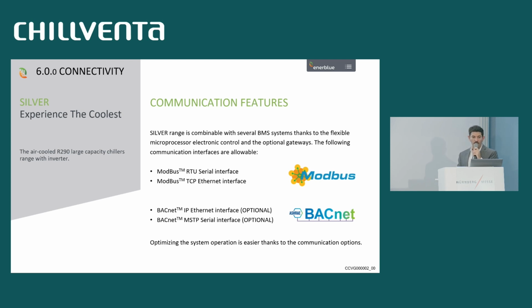Concerning the communication protocols, the unit is able to communicate via Modbus RTU or TCP/IP, as well as via BACnet IP or MSTP, which is a standard for our sector. The Modbus communication protocol is already standard in the controller. It is possible as an option to equip the unit also with the BACnet communication protocol.